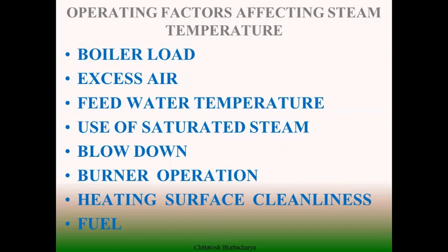Then how the saturated steam is generated in terms of quantity and dryness, that is also important, and how much blowdown is given to control the quality of steam, that is also part of the quantity of steaming, because generally 2 to 4% blowdown is essential.